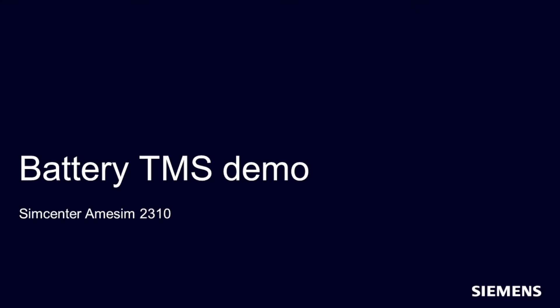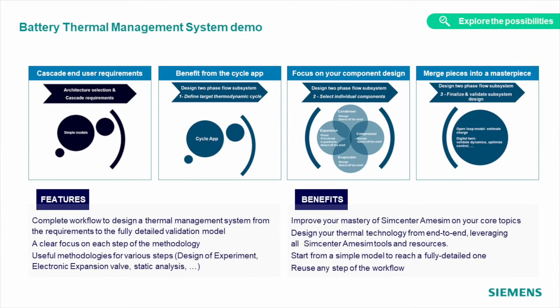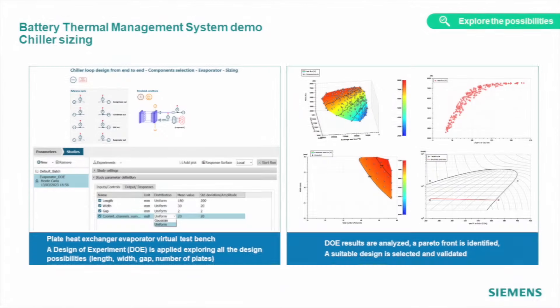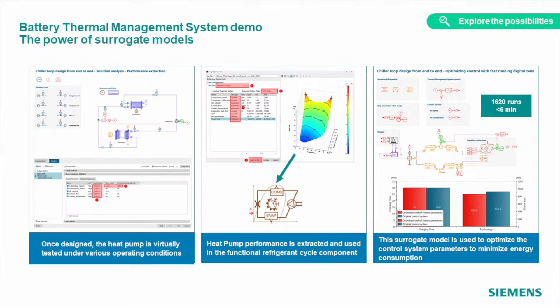A new battery thermal management system demo shows the approach of using Simcenter Amesim throughout the process of design of such thermal systems. Starting from the requirements and simplest model to determine overall needed cooling on a certain test profile, different tools and methods are used to make the model more detailed and precise. Once the model is validated, it's been reduced to improve CPU time but keep required accuracy, to then run large DOE and optimizations to achieve the best design.